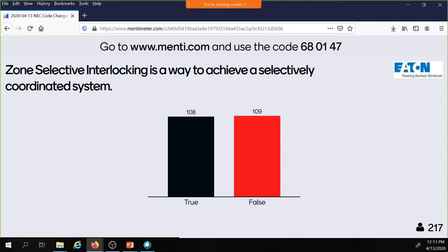And how we teach it is that we'll always say that these two breakers are connected together, and when a fault occurs downstream, the downstream breaker says, I got it, to the upstream breaker, and he holds those contacts closed while the downstream breaker does its job. And it sounds good. And to a point, it's right. But what they miss is that if you don't program the set points, when that fault occurs downstream of both breakers, and it's outside of the zone selectively interlocked zone of protection, they go by their programmed settings. There's no magical thing that is going to make the upstream breaker hold its contacts closed and ignore its settings. If you didn't set them correctly, they will open.